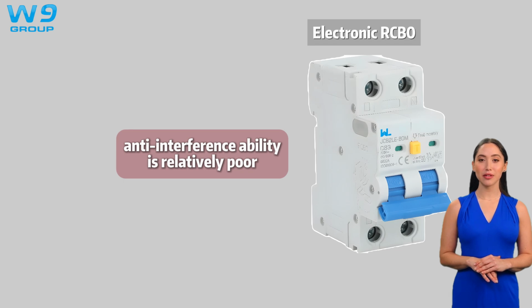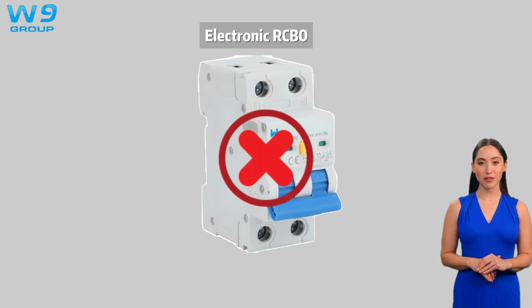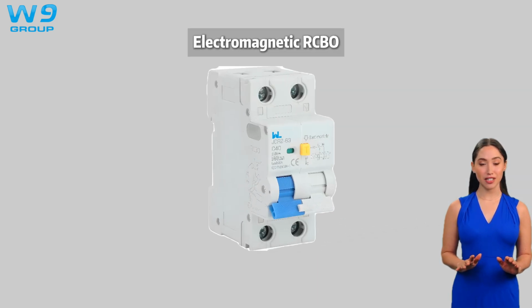Electronic RCBO is easily affected by power grid surge voltage and overvoltage, and its anti-interference ability is relatively poor. If the voltage is too low, electronic RCBO might not be able to trip, so electromagnetic RCBO is more reliable. But the price of electronic RCBO is relatively advantageous, the manufacturing difficulty is relatively small, and the mass production stability is high.